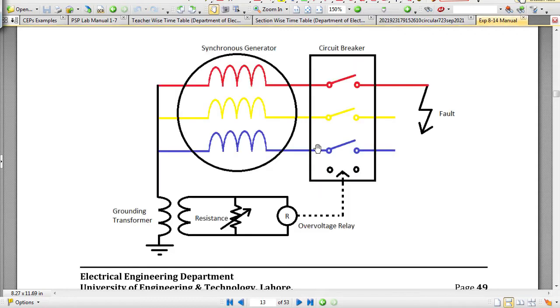In this experiment, students will study how we can insert a resistance or impedance in the neutral circuit of a generator to limit the fault current. This time grounding will be done through a grounding transformer.